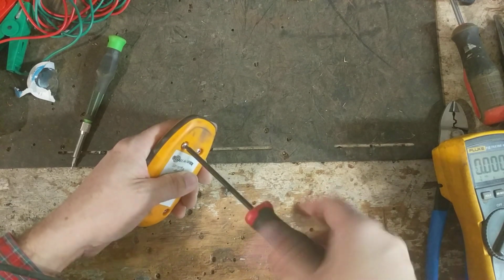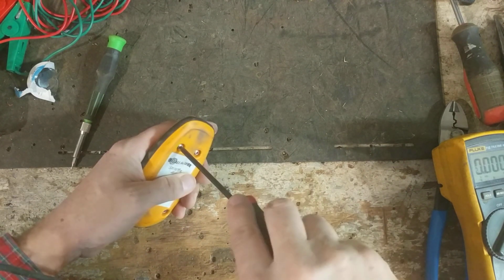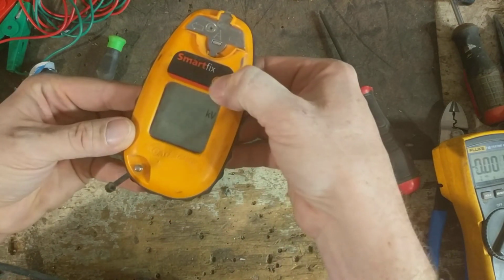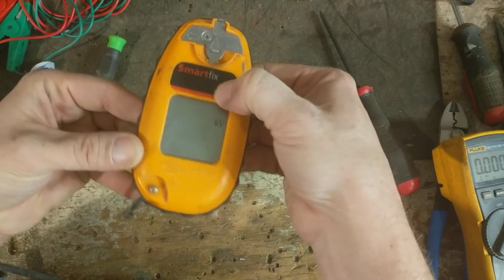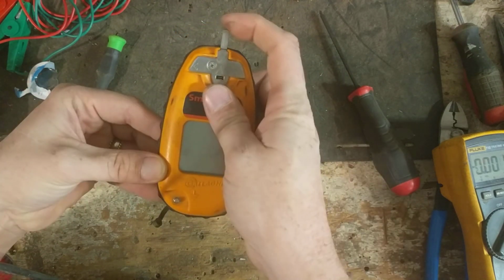You'll get a high amp rating out of a unit when there's no ground and no fence hooked up to it, since the tester's reading it wide open. See, it's switching between kV and amps. That little button still works up there.